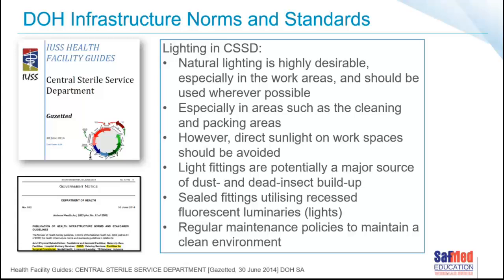Don't forget about light fittings, because they're actually a potential source of all sorts of build-up, dust, dead insects, et cetera. And so the guidelines talk about using sealed fittings that are generally going to be recessed. Normally, these are going to be fluorescent lighting. They also talk about the importance of having regular maintenance policies in place to maintain a clean environment around your lights. Have a look up at the lights next time you're in the CSSD, carefully, without injuring your eyes. But it's a good point. How many insects are floating around in our lights? An important point to bear in mind.